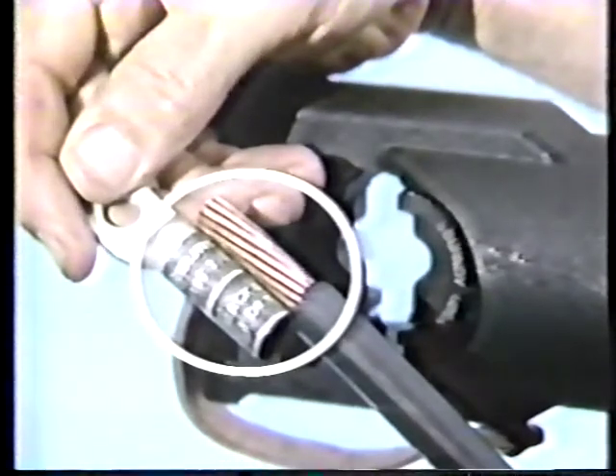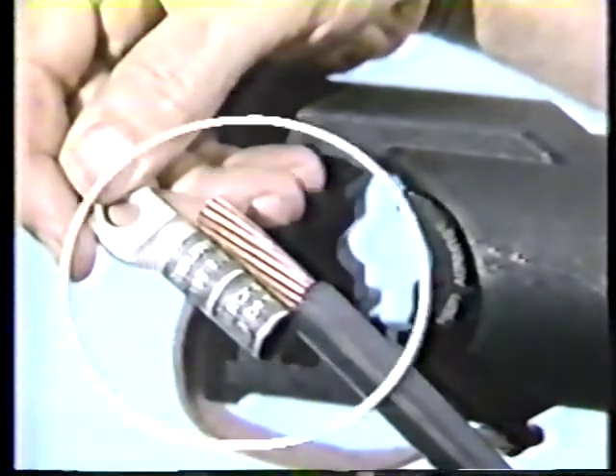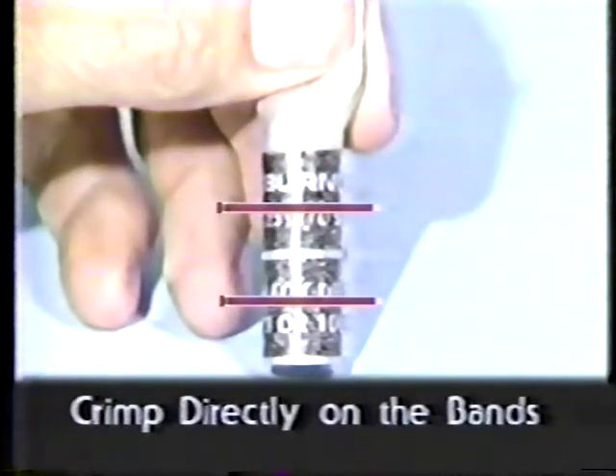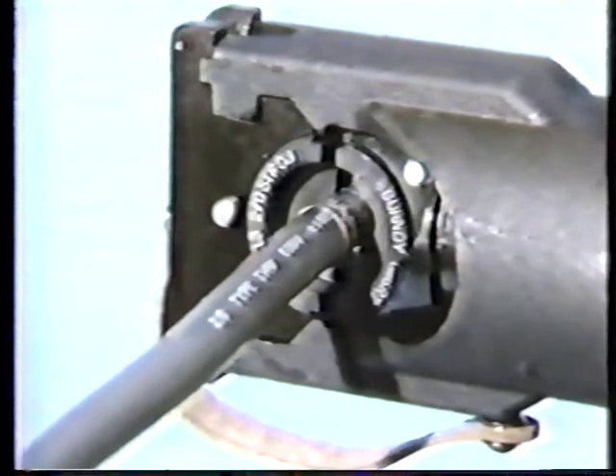When preparing a cable, Burndy's connector barrels serve as a convenient guide to remove the proper amount of insulation. Once the cable is prepared, place the connector in the tool with the tongue perpendicular to the die movement. Rotate the handle clockwise to rapid advance the dies and grip the connector. When doing this, be sure that the connector is positioned to crimp directly on the colored bands. After inserting the cable fully into the connector, pump the handle to complete the operation.